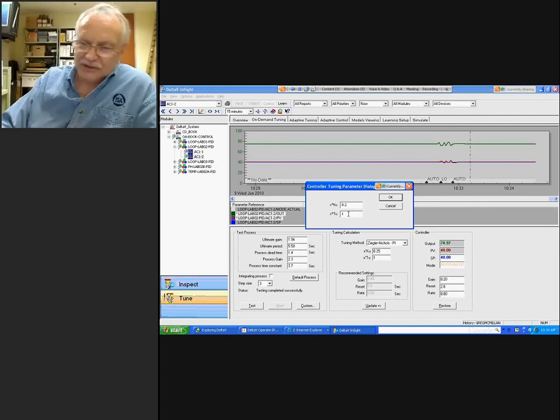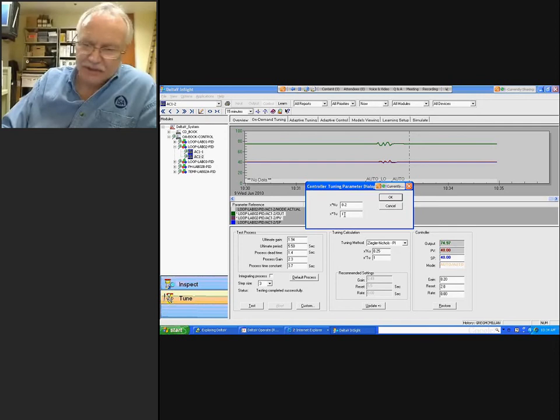Really, all they needed to do was to reduce the gain, and this effectively is cutting the recommended Ziegler-Nichols factor in half. Normally, the Ziegler-Nichols factor would be, I think, like 0.4 or something like that. And then people get hung up on a second significant digit, and things change in a process, whether it's due to the nonlinear valve, the nonlinear process, due to time and operating point. So getting too carried away with the two significant digits is kind of meaningless. So it's important in simulations, and that's where people get carried away with it.